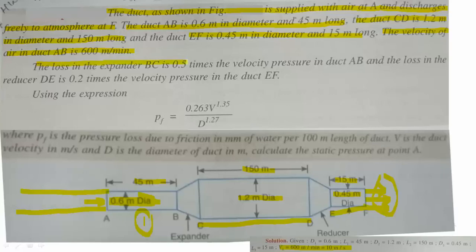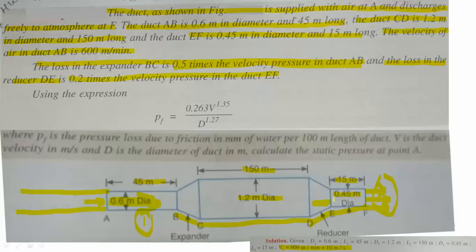The losses in the expander BC is 0.5 times the velocity pressure in duct AB — that is 0.5 times the dynamic head of AB. The loss in the reducer DE is 0.2 times the velocity pressure in duct EF — so 0.2 times the dynamic pressure of EF.